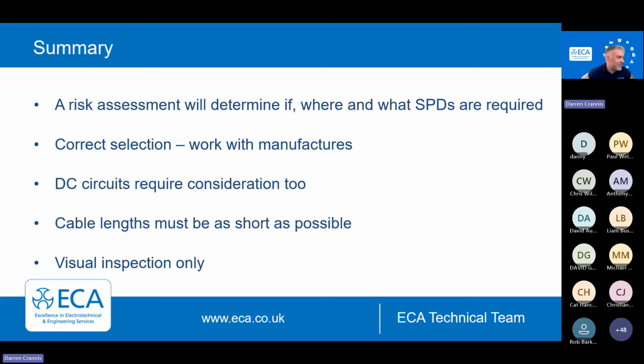So, in summary for SPDs, install these where your risk assessment states they are required. Often, it's good to work with manufacturers, because sometimes we over-engineer where SPDs are needed. And like I said, when you install one SPD, you might have to install several, especially if you've got multi-point distribution. Manufacturers can help you select the right SPDs in the right location, and you might actually be installing less than what you thought. So this is one of those occasions where you could really involve your manufacturer.